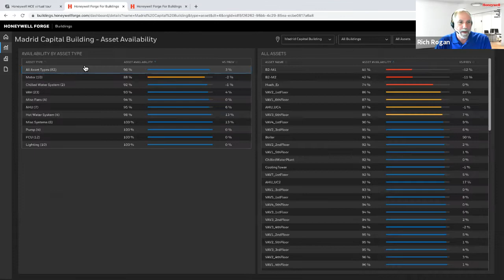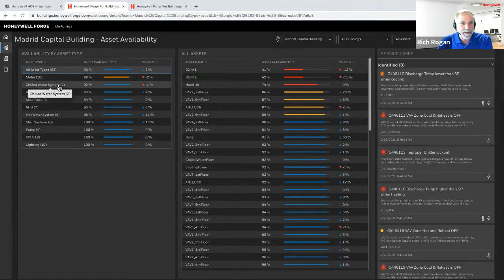Service cases are essentially context sensitive as you move around through the Honeywell Forge environment. Right now we're seeing a summary on the left of the various assets in the Madrid facility, some meters, chilled water systems feeding 7 air handling units, as well as a number of VAV boxes out there. But as I move around the system, you'll see that the service cases on the right, generated through our predictive maintenance solutions, are raised to the top.